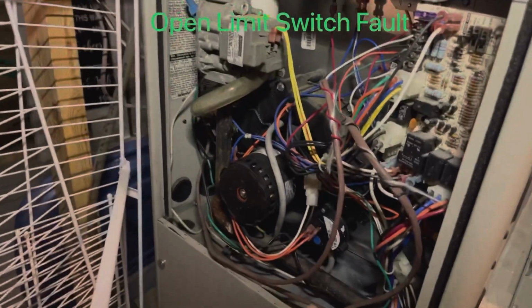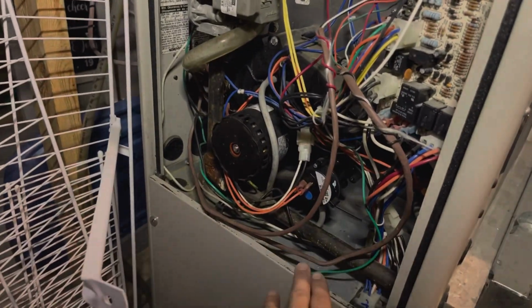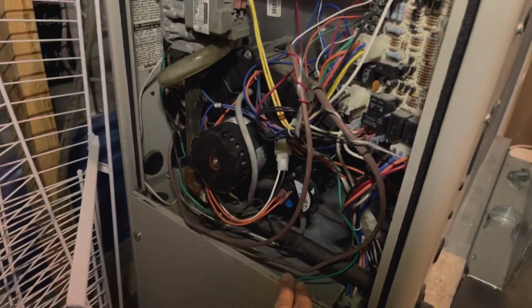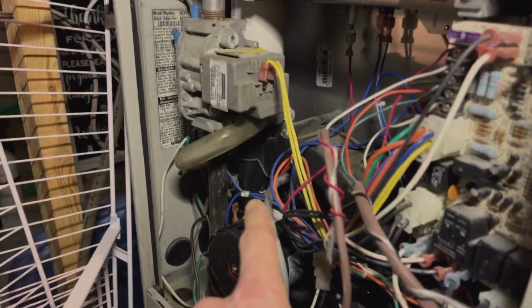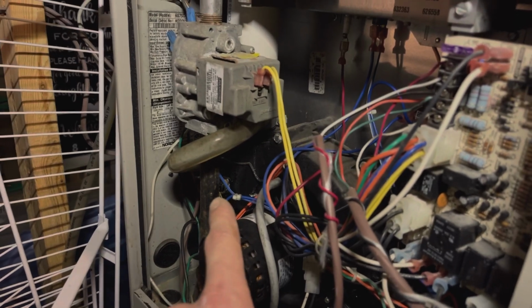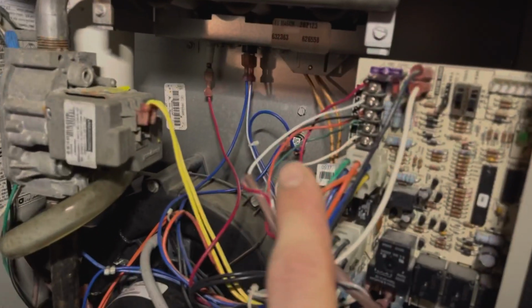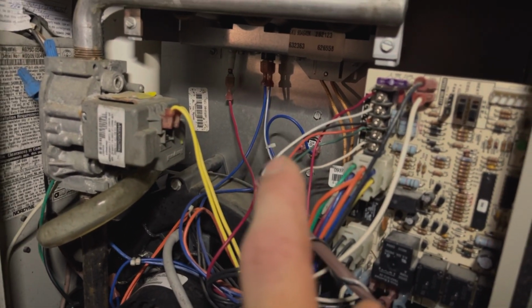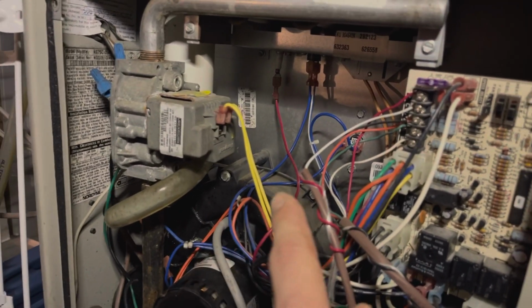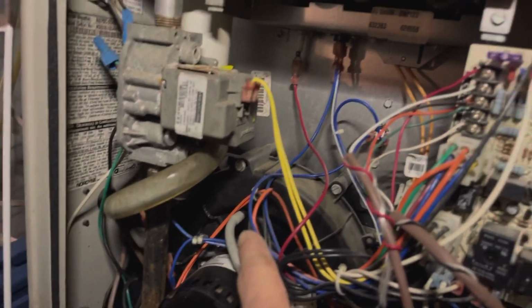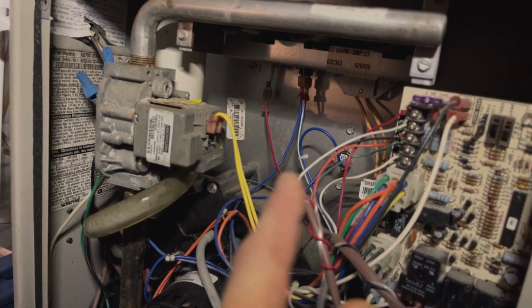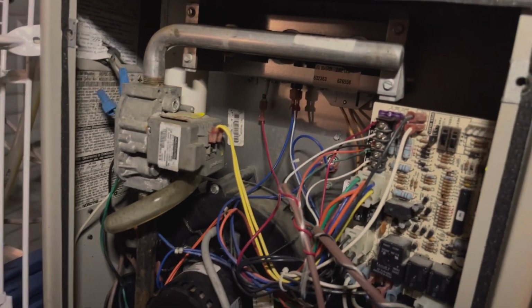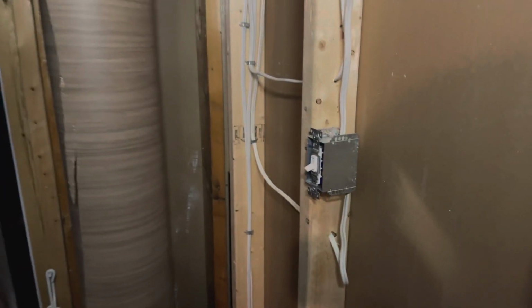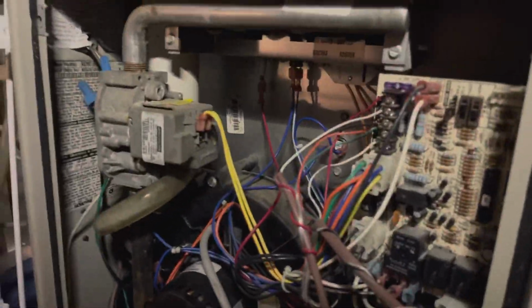You can hear the blower motor is on. So the blower motor seems to be functioning okay. Now I'm gonna turn this furnace off and plug that back in. And if I did the same for these other limit switches, it would do the same thing. These limit switches, all three are lined in series, which means they're all wired together and back to the control board. So I switched it off, and we'll come back over to the furnace, and now I can plug it back in.